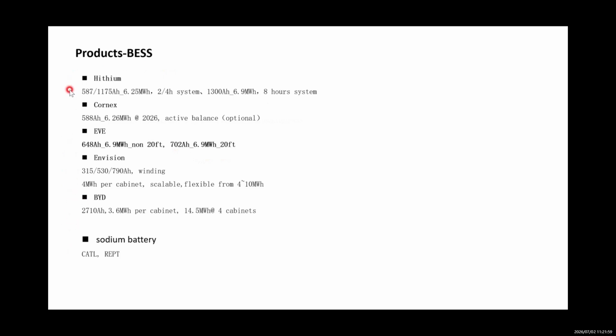First is Hithium, which launched a 6.25 megawatt-hour battery container suitable for 2 hour and 4 hour systems. The battery cell capacity is 587 ampere-hour for the 2 hour system, and 1175 ampere-hour for the 4 hour system. Also, Hyperstrong launched a new product, 6.9 megawatt-hour, using 1300 ampere-hour battery cells. It's a long duration system, 8 hours, which will help fulfill long duration energy needs in the future. This is their new product.